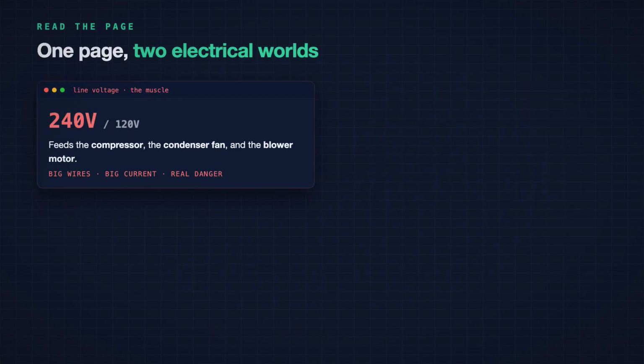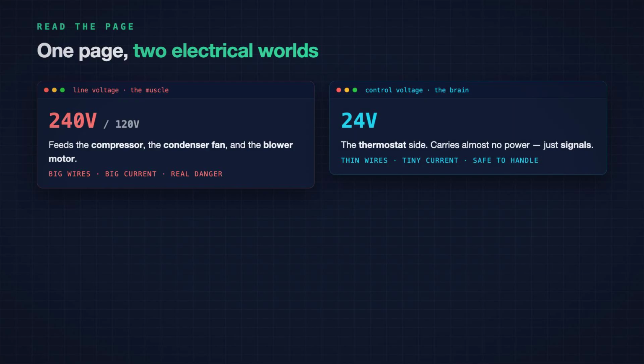Here is why an HVAC print looks scary. There are actually two different circuits drawn on the same page. The first is the line voltage side. That is the muscle, 240 volts, or sometimes 120, feeding the compressor, the condenser fan, and the blower motor. Big wires, big current, real danger.